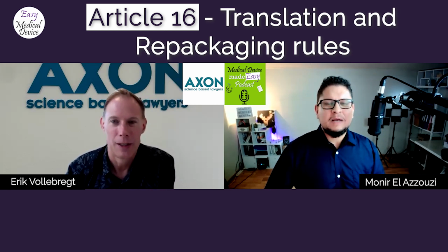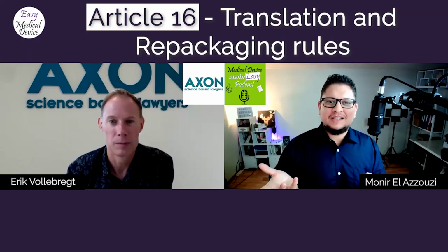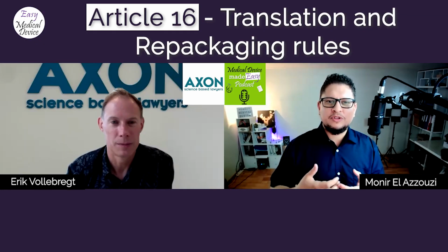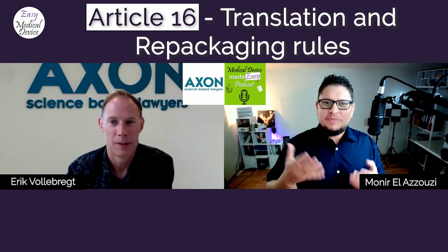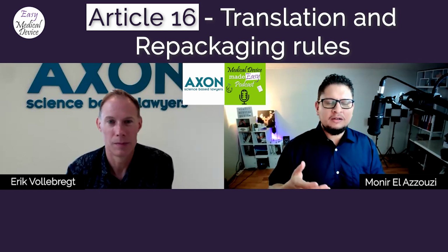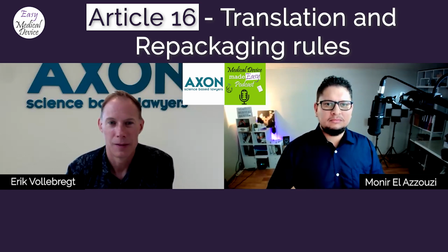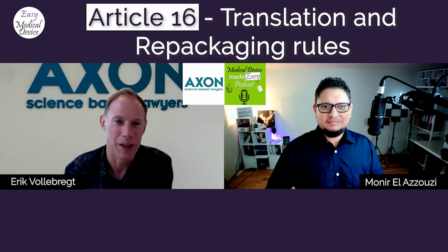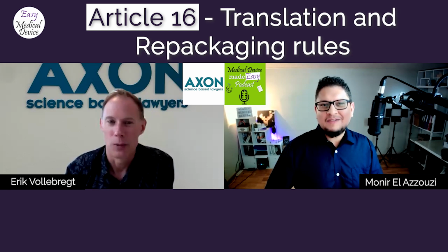Exactly. But one thing, I don't know, is it applicable as of the 26th of May 2021? Because they have no certificate now, so it's a new thing. The importers and distributors don't have a certificate. So can we say that it should be applicable now? Now they have to have this certificate, or is there some timeline here? Well, there's not a transitional regime in the MDR for Article 16 activities. So now they have to have it. Yeah, basically, if you engage in the activity, you should have a certificate for that by now.